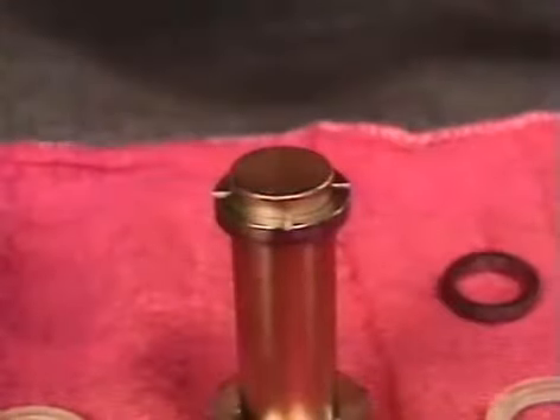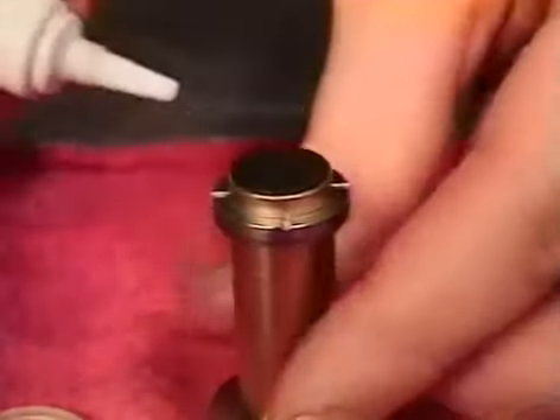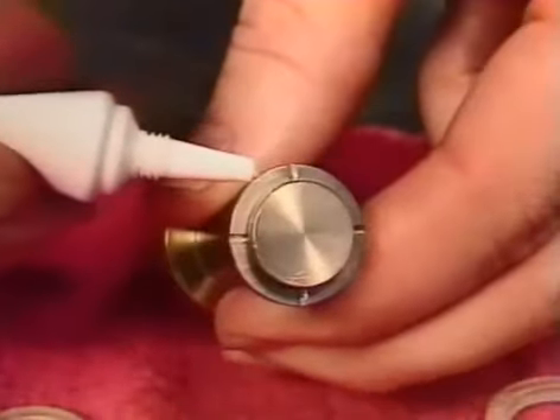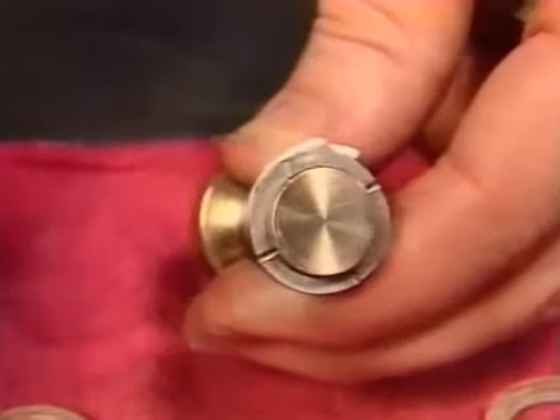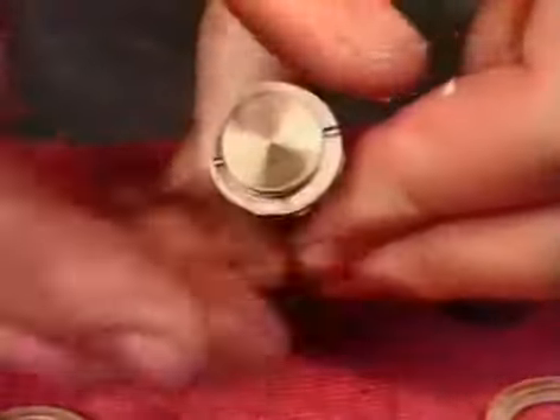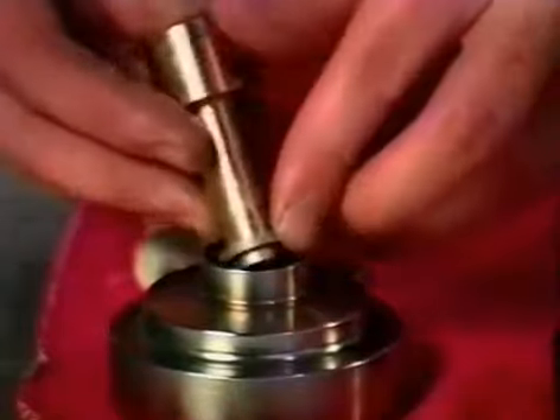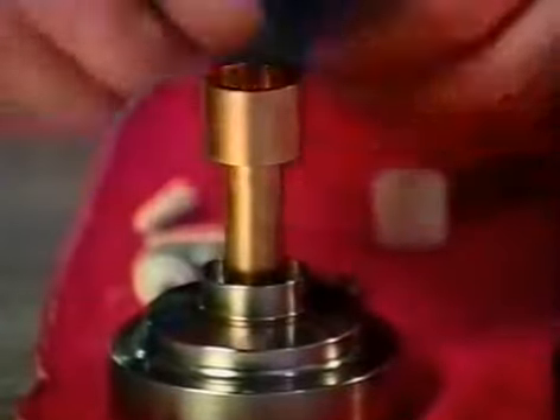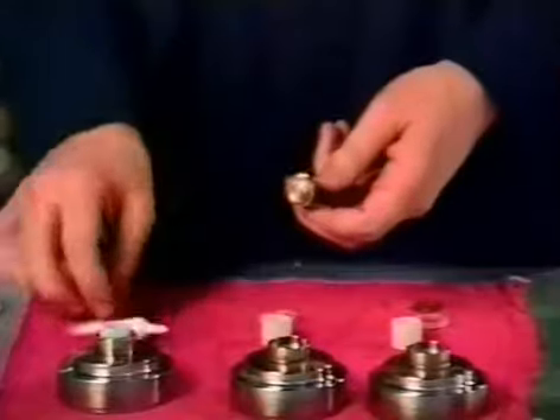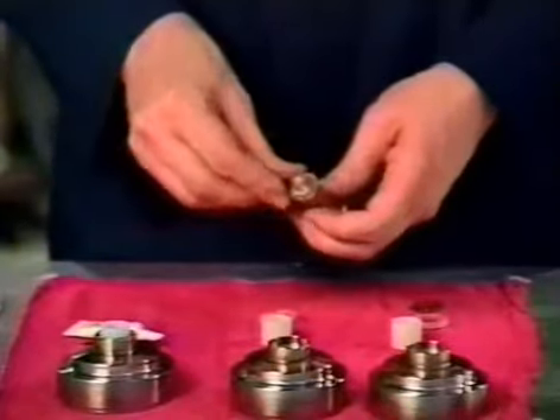Lubricate the backup ring with white food-grade O-ring lubricant. Install the backup ring into the backup ring housing. The slots in the backup ring will face down toward the bottom of the backup ring housing. The backup ring should fit tightly into the backup ring housing, but it shouldn't be a press fit.